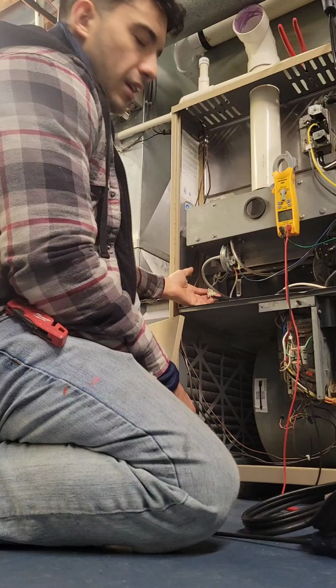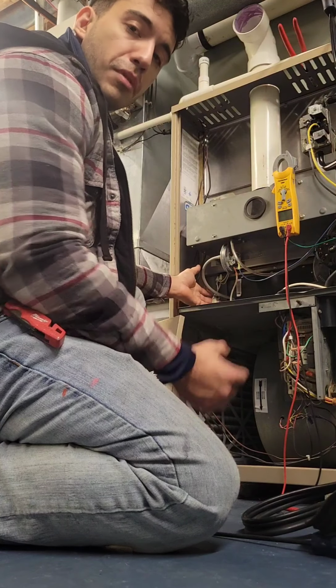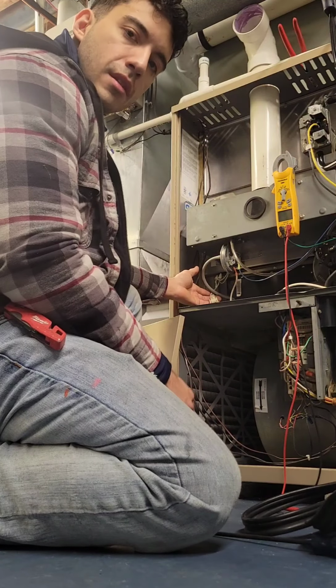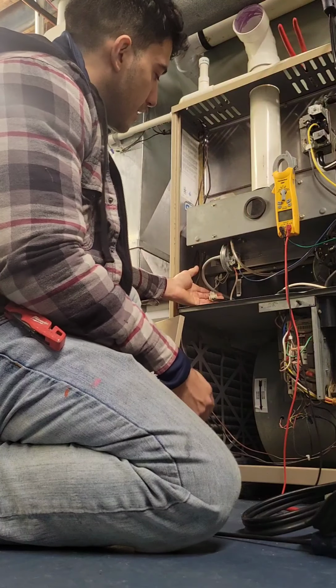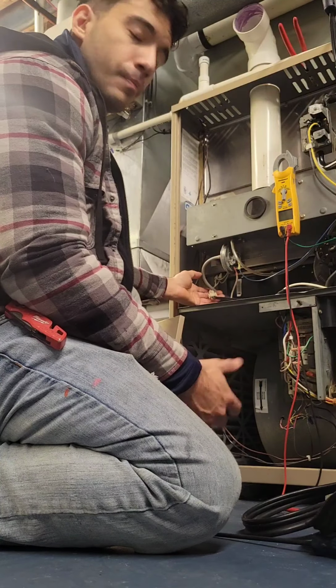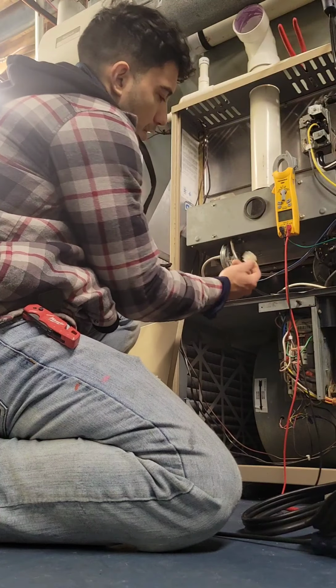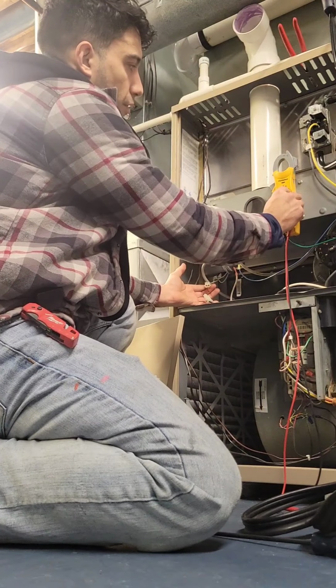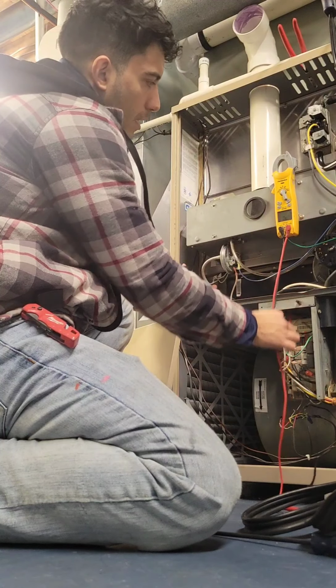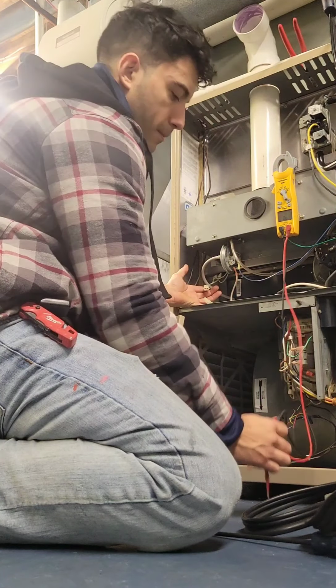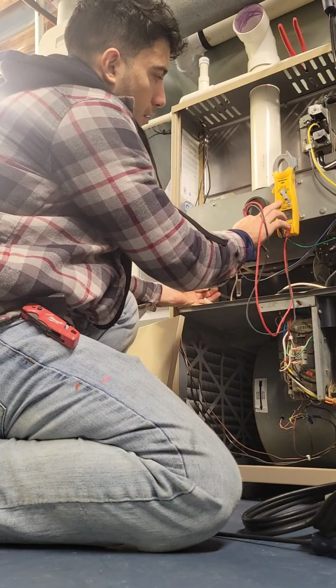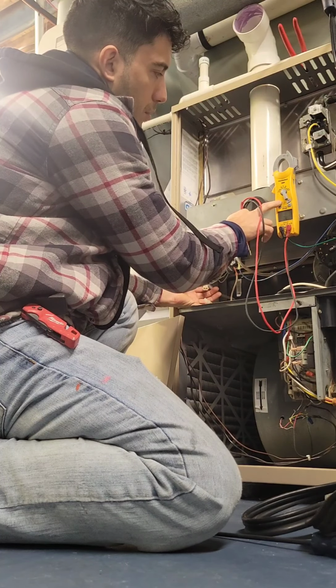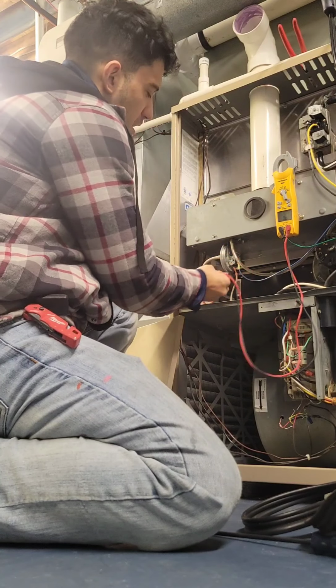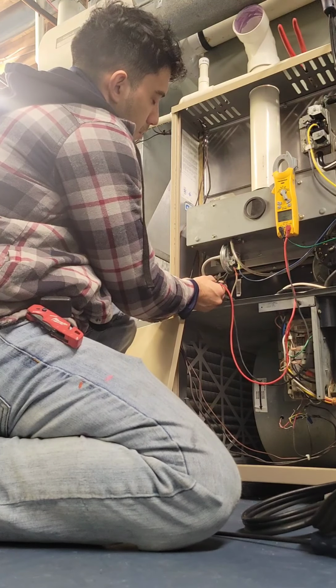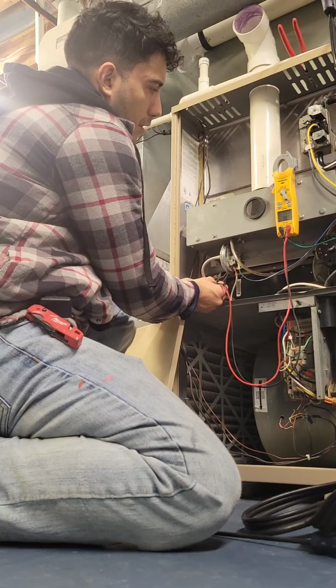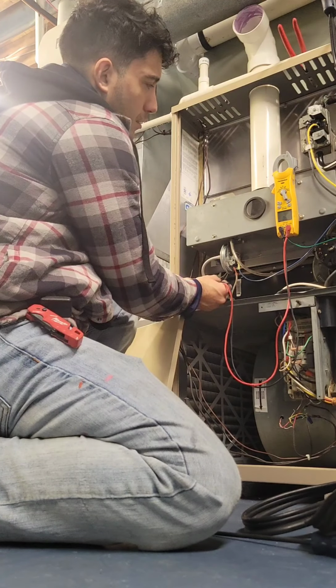So we obviously checked the resistance of the igniter. You can tell this igniter has been replaced once before because it does have wire nuts attached to it, and they cut it in splices. So we want to make sure that resistance is good. So we usually disconnect right here, at the actual igniter. You'll take your meter and verify the resistance between the 2 points. So all we want is resistance. Usually a cold igniter, I will call it, is about 89, almost 90 in resistance.